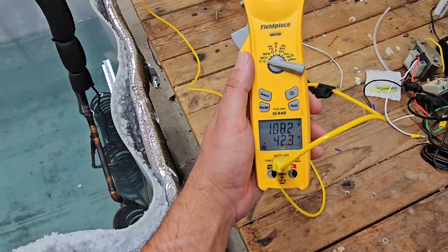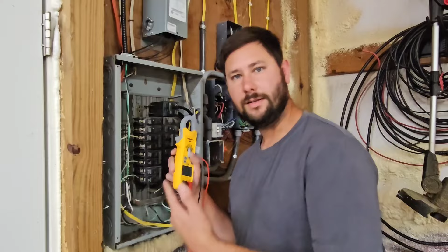Now, to figure out how much this costs to heat our water, we need to take a few measurements with the meter. Let's do that. So measuring the temperature of the gas pipe, it's 108 degrees, so around 110 degrees. We're going to take our meter now and connect our leads. We're going to turn it to volts AC. We're going to use our meter leads, and here's our 30 amp double pole breaker that powers that mini split.